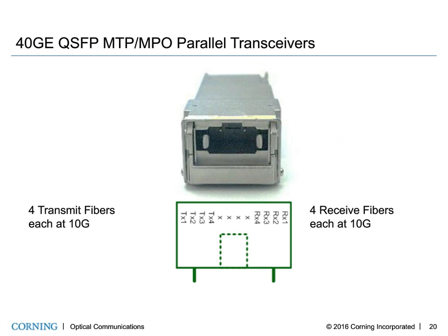Real quick, I want to show people this because it's going to help explain the next slide a little bit. When we talk parallel 8 fiber, which we're going to see all over the roadmaps, it really is a 12 fiber MTP with no fibers in the middle 4. That's the spacing they use, and that's the spacing used across the industry. So you have 4 transmit fibers on one side of the MTP, nothing in the middle 4, and then 4 receive fibers on the other end of the MTP. Whether it's 4 by 10 for 40 gig, or 4 by 25 for 100 gig, or at some point 4 by 100 gig for 400 gig, that is the roadmap that all the parallel solutions are driving towards.